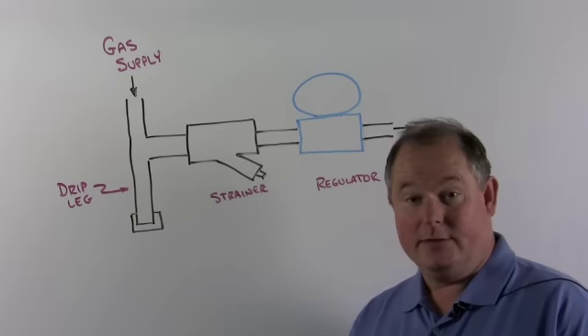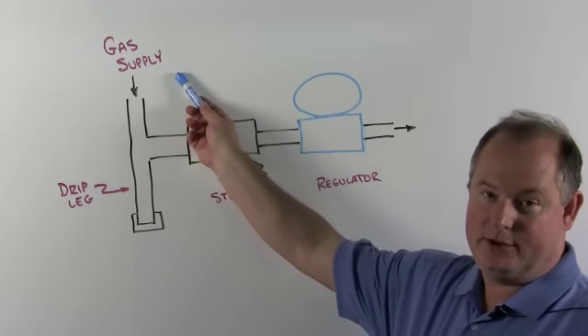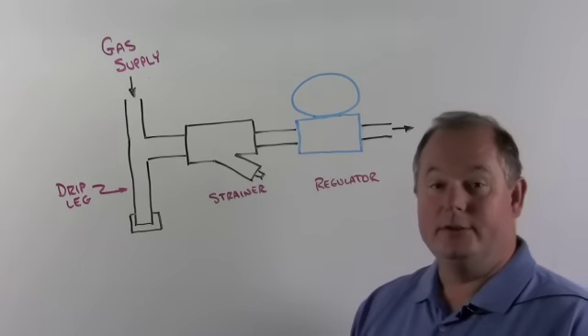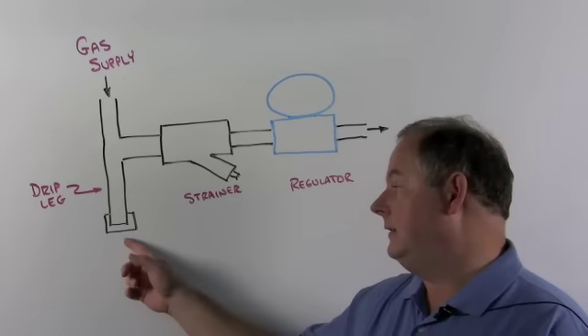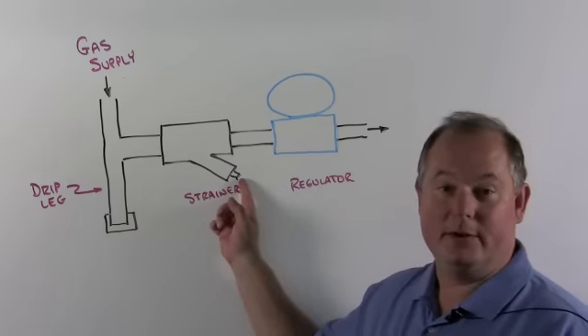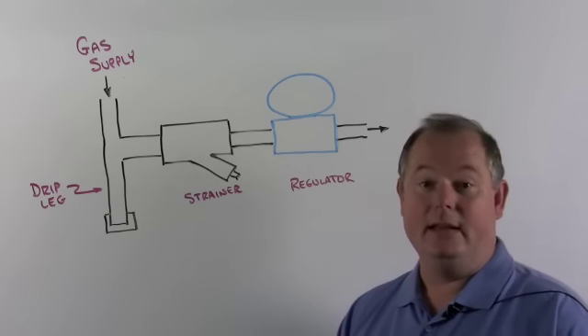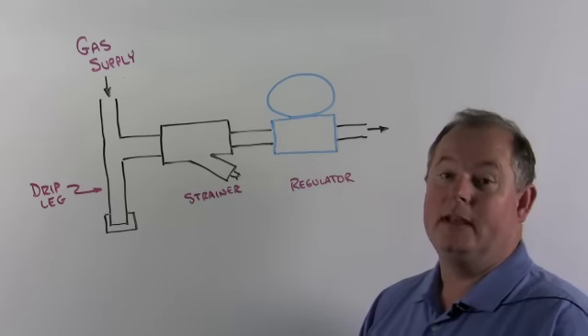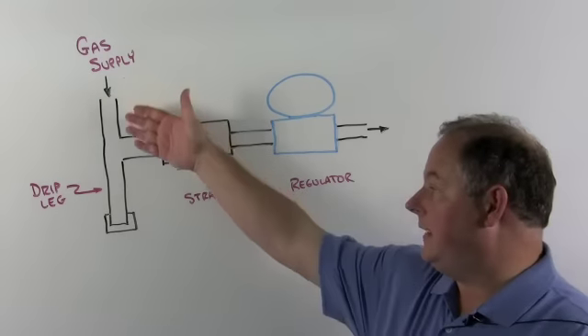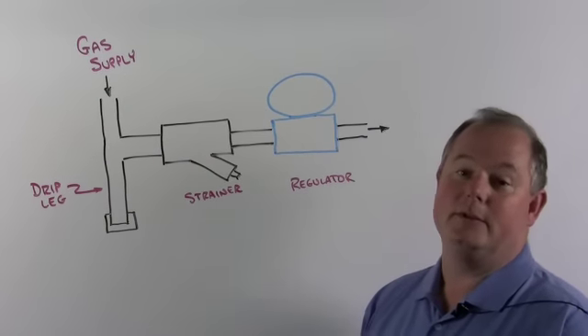Best practice for startup, we naturally have to have the high pressure for our leak pressure test on the gas supply. Do yourself a favor. Relieve that pressure out either the drip leg or out this part of the strainer. Let it do the work. You'll have pressure in there. Might be a few PSI. Might just be inches of water column. Let it do the work and move all that debris through the system and out that open hole safely away from the regulator.